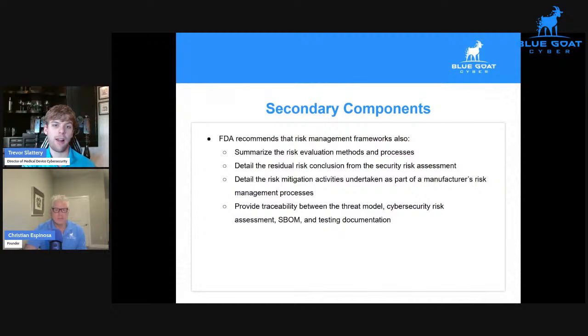Now, there are some standardized safety risk assessment methodologies that are covered by the FDA and part of ISO 14971, but there are not really any standardized frameworks that cover both security and safety. So having a method to evaluate them carefully can be good, and it often needs to be developed internally. Typically, what we look at is a blend of CVSS for that exploitability metric, and then modifying the impact metric to instead look at how it can harm a patient. So that's meeting both of the needs of what the FDA wants to see. They want to see something standardized for a risk evaluation method, and they also want to see it consider patient safety.